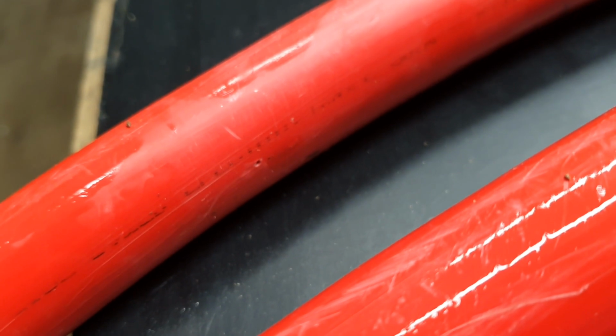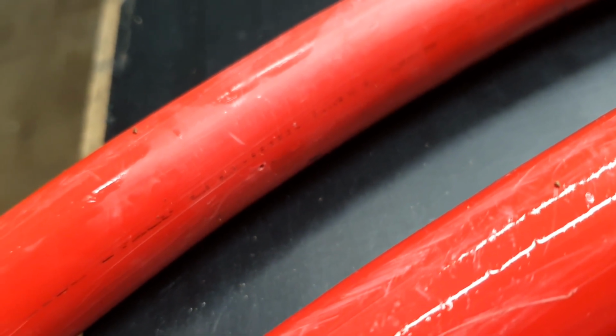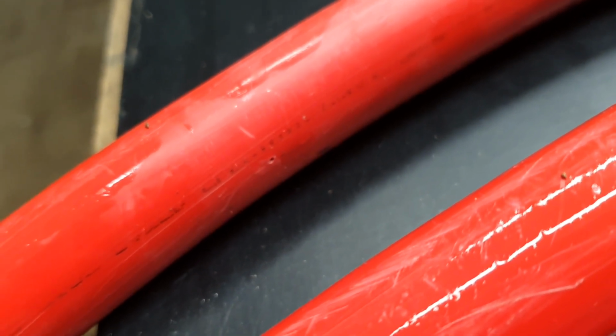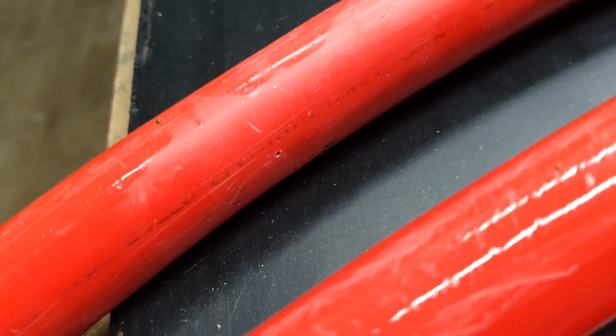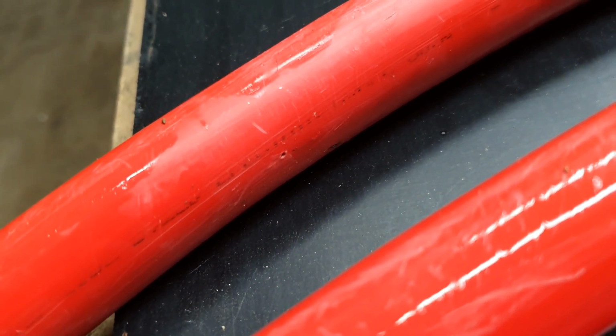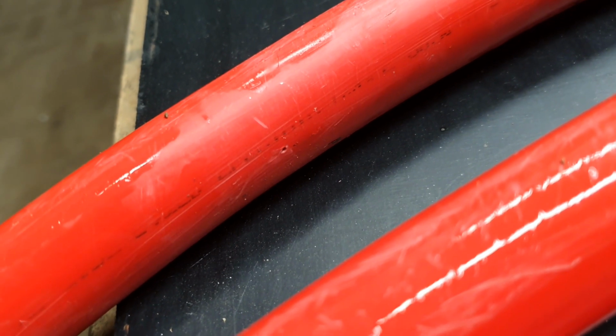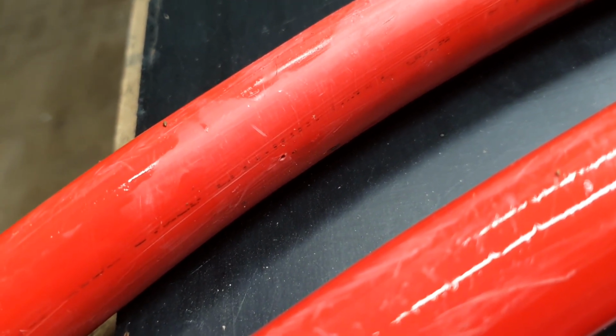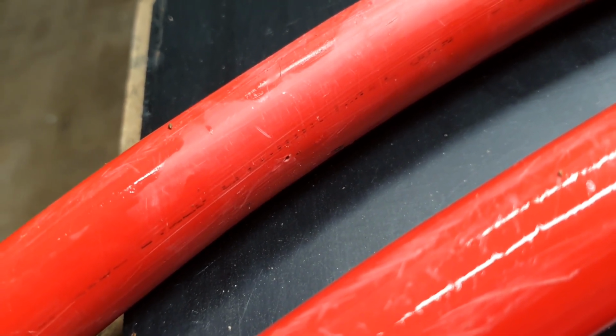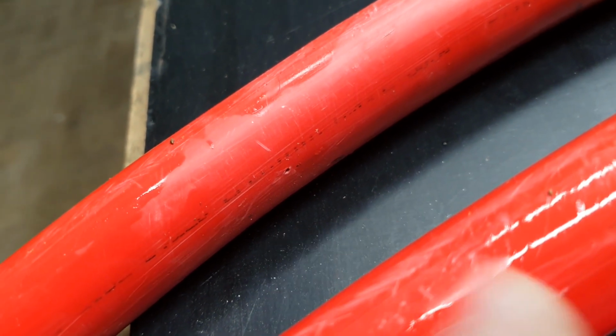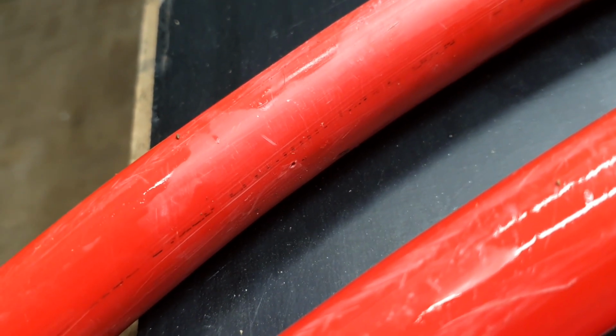It was fluctuating between about 0.8 of a mega ohm and up to about 2, so it was floating around in that sort of zone, which is not a good zone to be for a fresh cable, even if it is sort of in the ground a little bit. Yeah, so that was probably the worst bit of damage on the cable that I found.